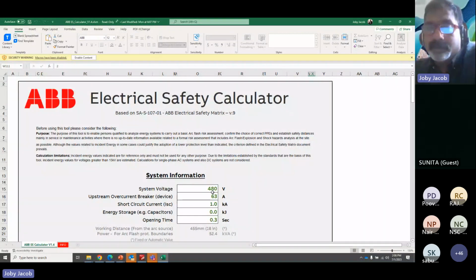So ideally when you do the calculation, there are 4 parameters we are considering. One is the system voltage, which we can get from the nameplate, and your upstream overcurrent breaker device current. What is the current rating of the upstream breaker, whether it is 100 amps or 200 amps, basically your bus bar rating. And the third parameter is the short circuit current carrying capacity. What happens if a short circuit happens? So if you have a short circuit, for example, a 2000 amps or 1500 amps bus bar can get up to 15 to 20 times the maximum value in the short circuit. And it adds on if you have inductive loads connected to that, right?